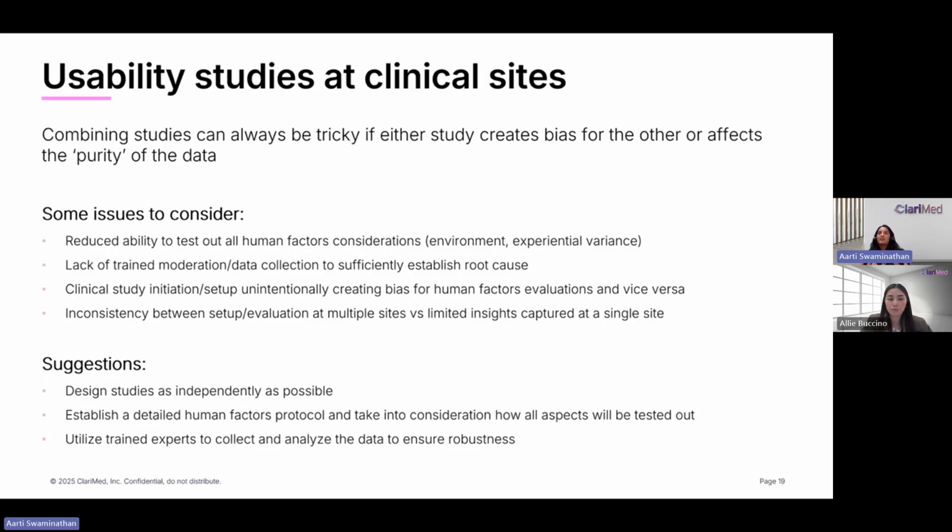So all that to say, if there is training that you are providing as a minimum before performing this test for the very first time, that's additional justification that you can use to show a reduced need for human factors validation, or be able to build that into your study and have better outcomes as a result, because you've accounted for what you're providing in real life.